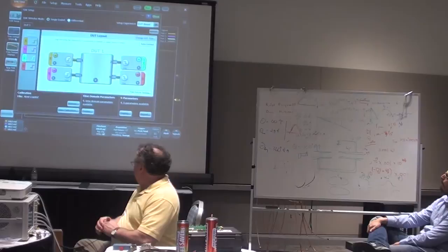So you can interrupt under this, and we want TDR, TDR. And it does a click, click, click. And the first thing it asks you is, oh, you have a four-port analyzer.